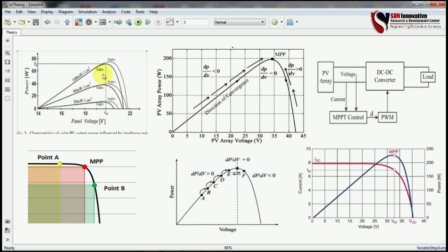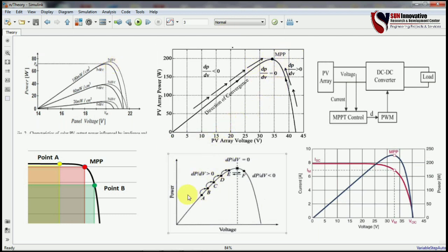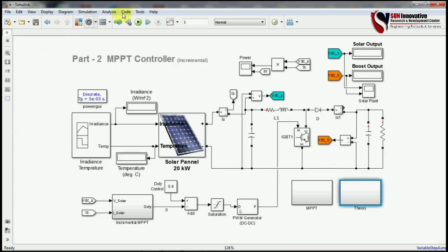In this basic concept of MPPT technique, you can see each graph has a maximum power point at the top of the IV characteristics. The X and Y axes show power and voltage. This is a graph of different irradiation levels and the maximum power gained from the output. Our aim is to generate maximum power from the solar system at the point where dP/dV equals zero.